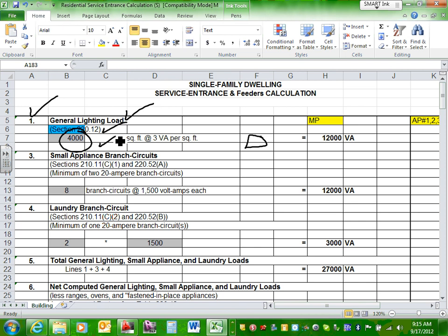What you need to do is justify it. So when you burn the building, and they send somebody like your friend Chad as a forensic expert to see what happened, and I'm not talking about this apartment, a real project, and see what did you do to come up with a 2,000 amp switchgear? Well, here's my steps, step by step. If you have this referenced by the code, your chances of winning a case are much higher. Otherwise you say, well, the last project that we did was like this, so I put 2,000 amp. Does that make sense? Why we do what we do?